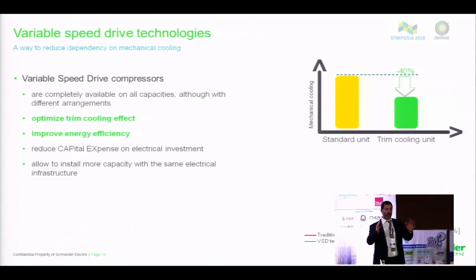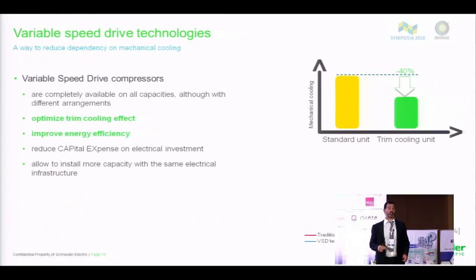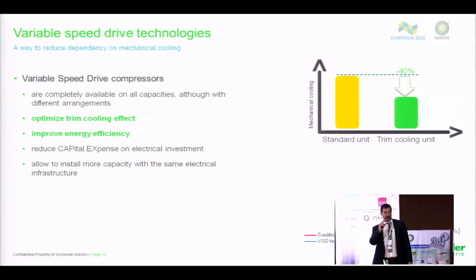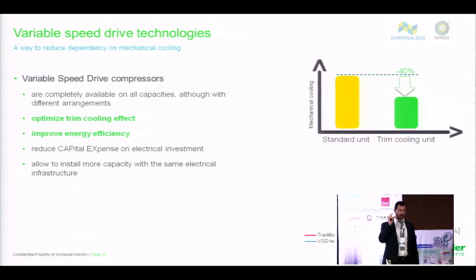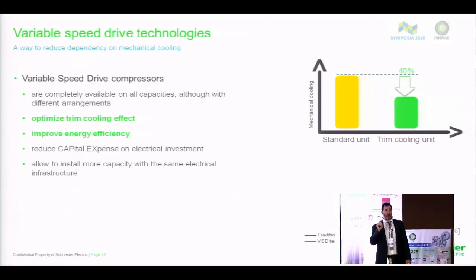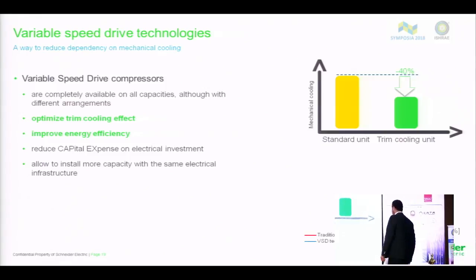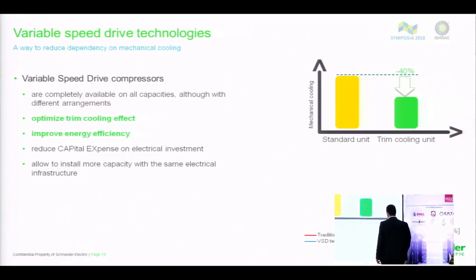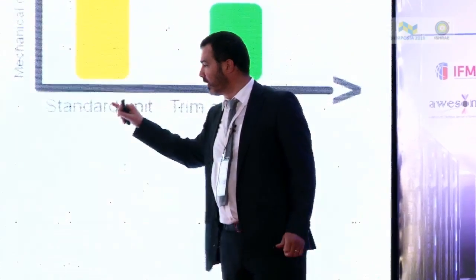dissipates the large part of the capacity by the heat exchanger, and the compressor only a small portion. This means that the compressors are usually smaller and more working at a lower condition than in any case. So, if the concept is not to have a standard cooling, but a trim cooling, a compressor that trim the capacity, so adjust the capacity, not dissipate the entire capacity.